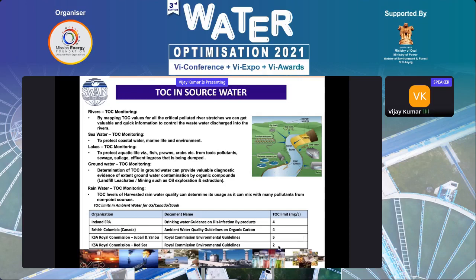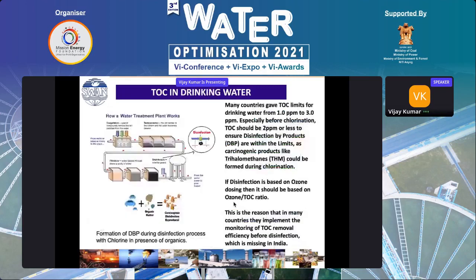So there are many countries that have given limits for source water of around 4 to 5 ppm, but in India this is missing. And when it comes to drinking water, I see a lot of NTPC plants have their own drinking water plant for their township supply. In drinking water also, TOC limits are defined between 1 ppm and 3 ppm. This is for the disinfection byproduct rule, to control trihalomethane, which is a carcinogenic byproduct you can anticipate from chlorination. So to ensure that, you need to make sure TOC is removed before disinfection. TOC should be less than 2 ppm, so that even if trihalomethane forms, it will be within the acceptable limit.